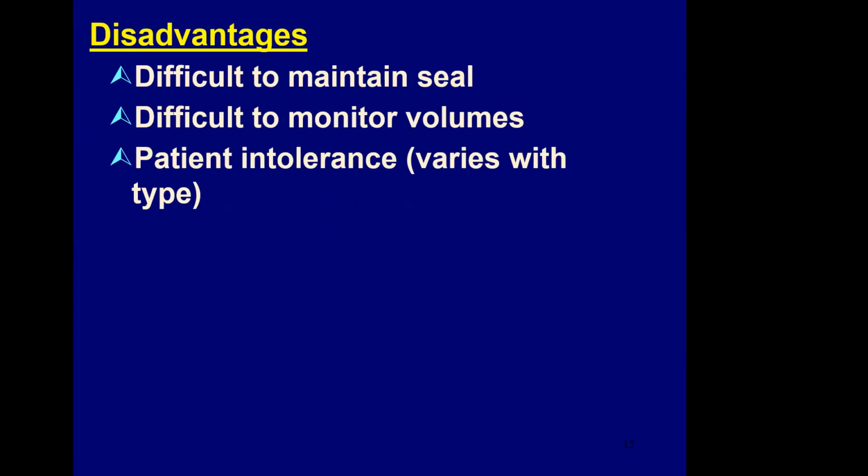Okay, other disadvantages. It is difficult to maintain a seal. It is difficult to monitor volumes, although it is doable. And there may be intolerance from the patient that varies with the type of negative pressure ventilator.